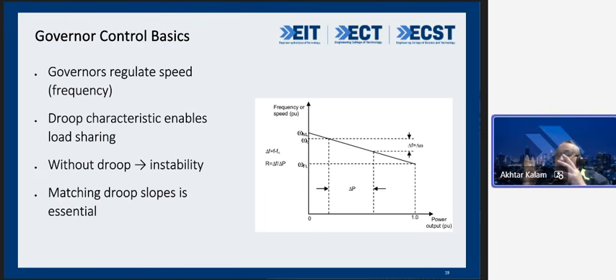So the droop control, the droop characteristic of the machine that you see in the figure I've shown you, if you look carefully, that is the one enabling load sharing. Without droop, I would have instability. And that slope is essential, my friend, that slope is essential.